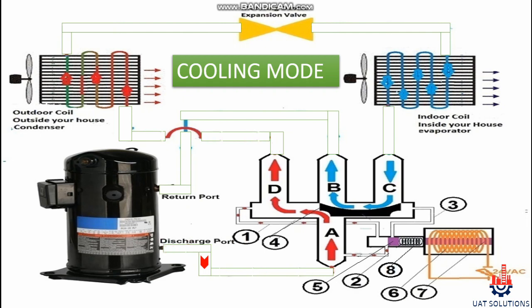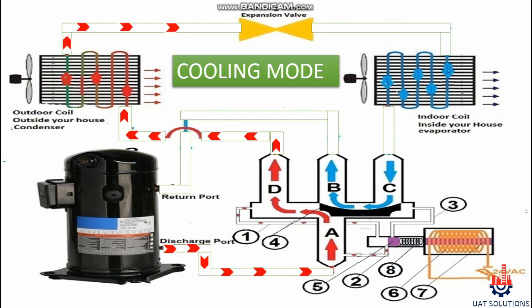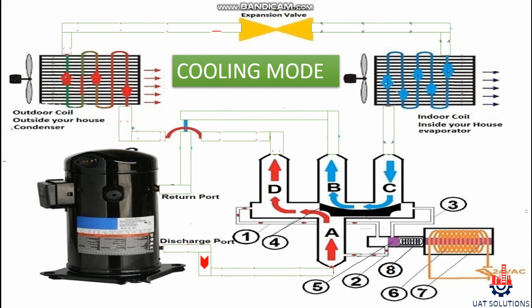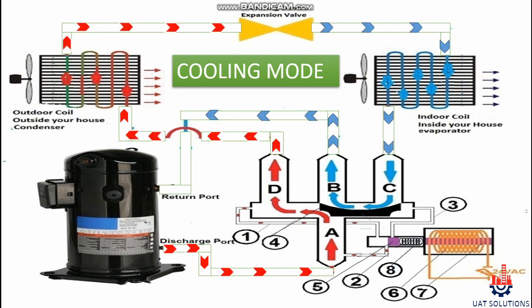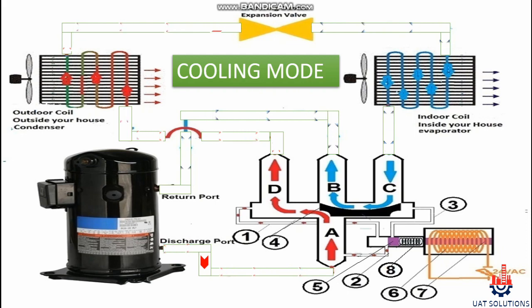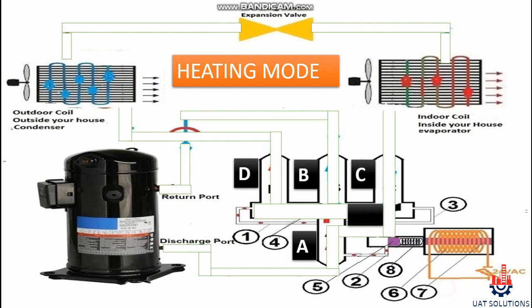The refrigerant goes to the condenser via port D. After condensation, refrigerant passes through the metering device and is sprayed into the evaporator coil, then enters the four-way valve port C, passes through port B, and enters the compressor suction line. This cycle keeps repeating as long as the compressor stays in operation.